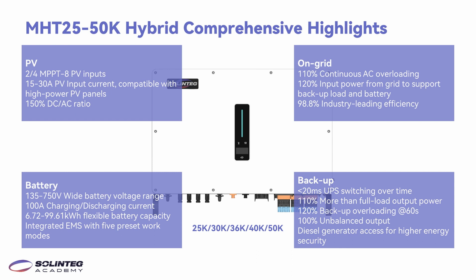As for the on-grid side, we support 110% continuous AC overloading, enabling high power generation. For example, a 50 kilowatt inverter on-grid side can output 55 kilowatt continuously, and it can import 120% power from grid. So more power from grid can support the backup loads and charge the battery. So we have the industry leading efficiency, 98.8%. In backup side, the on and off switching time is less than 20 milliseconds.